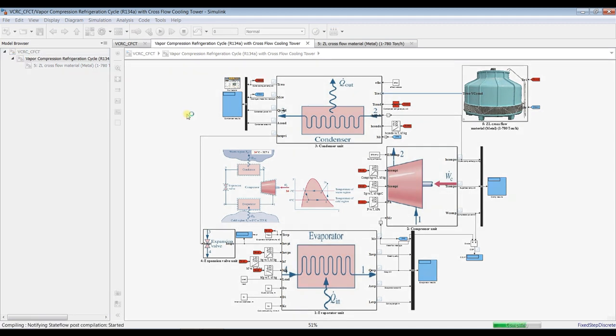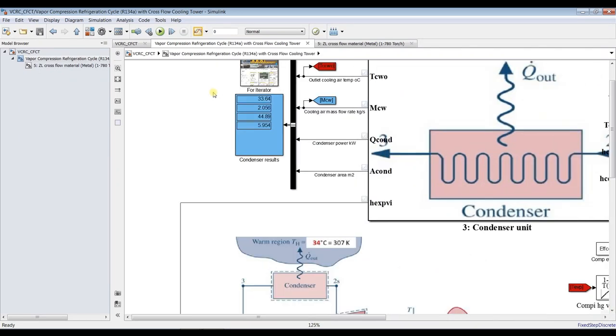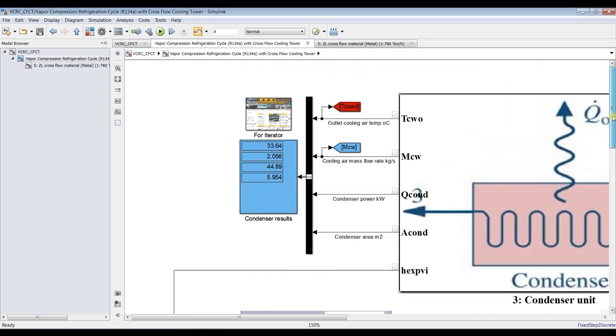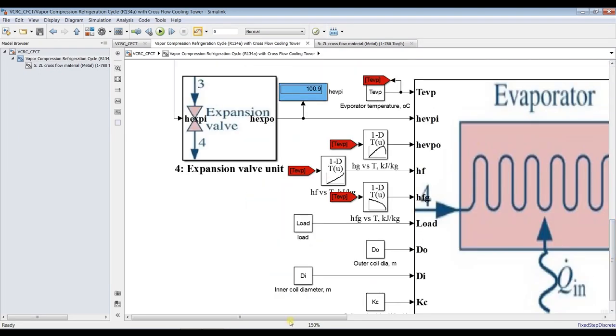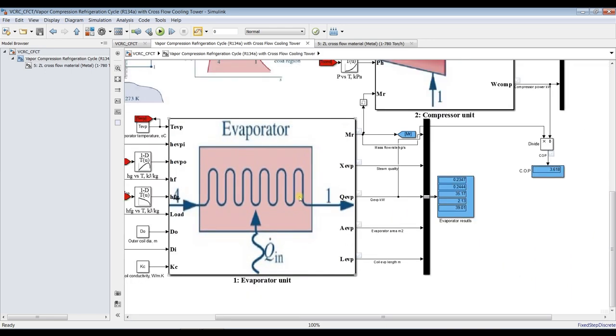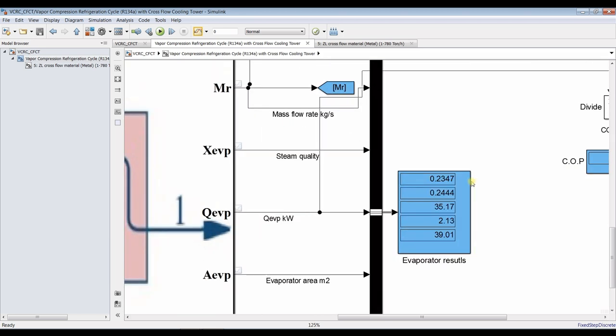And we're going to discover the following. Okay, under such circumstances, we have to get our results. As you can see here, let's begin from the evaporator unit. Let's begin from the evaporator. This is the cycle mass flow rate, the refrigerant mass flow rate, okay, so the cycle. It's around 0.2 kilogram per second, 0.234 kilogram per second.